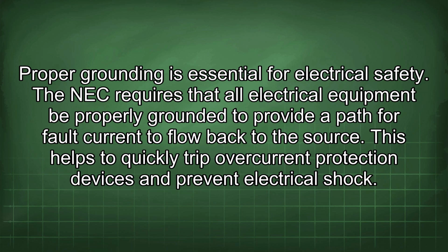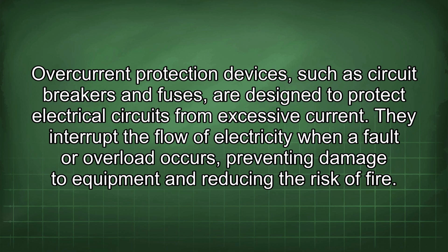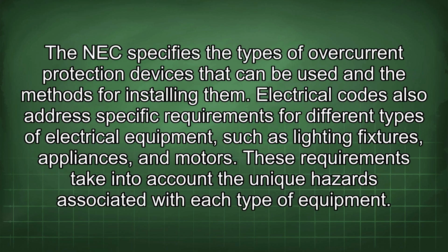The NEC requires that all electrical equipment be properly grounded to provide a path for fault current to flow back to the source. This helps to quickly trip overcurrent protection devices and prevent electrical shock. Overcurrent protection devices, such as circuit breakers and fuses, are designed to protect electrical circuits from excessive current. They interrupt the flow of electricity when a fault or overload occurs, preventing damage to equipment and reducing the risk of fire.